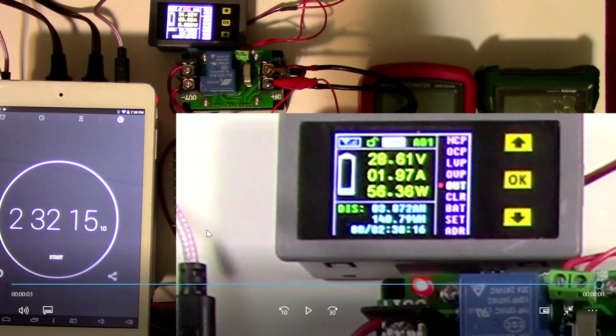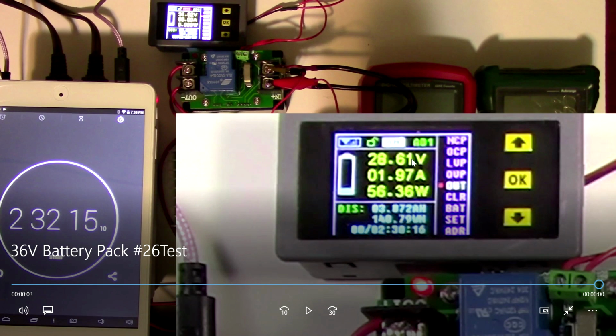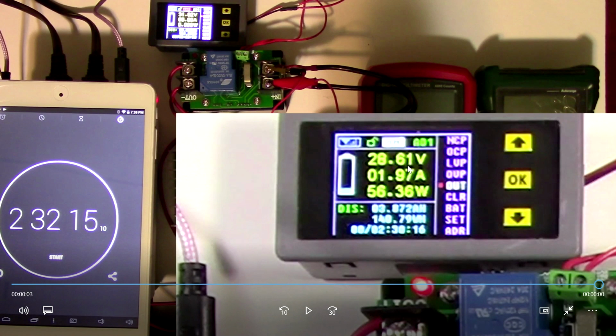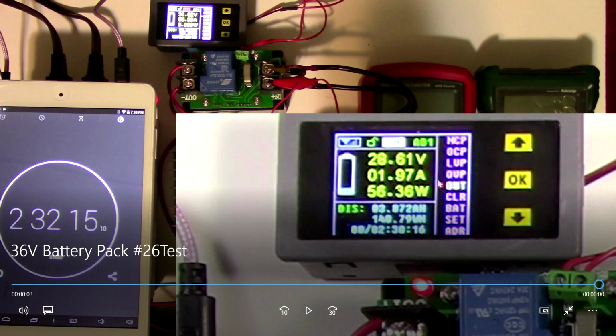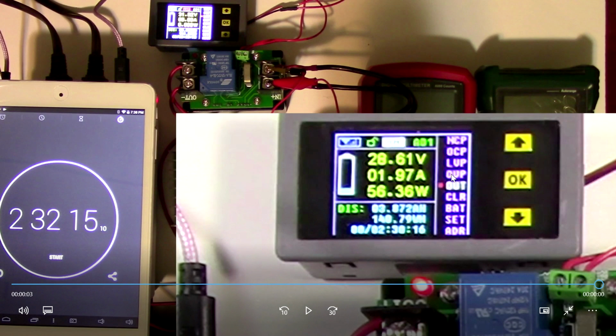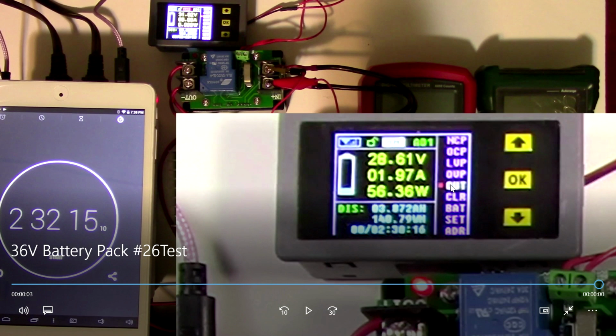My results were basically the cutoff point was 27.8 volts, and I show here 28.61 on the zoom in, but that's because the battery recovers a little bit after it cuts off. And you can see here that I was running about 1.97 amps at discharge rate, so that's pretty good. But like I said, my low voltage protection kicked in and shut it off at 2 hours 32 minutes 15 seconds.